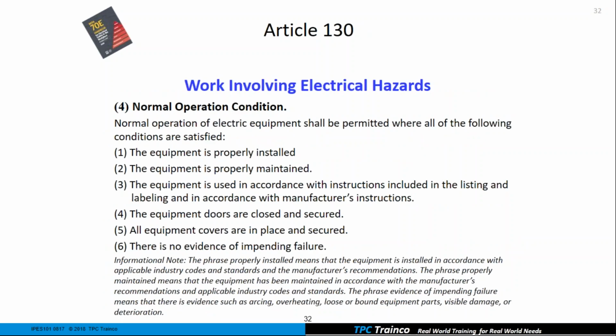Article 130, which is pretty much the heart of NFPA 70E, and the first change we see in there is normal operating condition. There used to be 5 conditions that we had to satisfy before we could go up and operate a piece of equipment normally, but now they've added one here. Number 1 was always there, properly installed. Number 2, always there, properly maintained. Properly maintained, by the way, in my opinion, is tough because it has to be maintained in accordance with the manufacturer's instructions and applicable industry codes and standards. I always use, for an example, a molded case circuit breaker. How many of us go out and test the torque on that once a year? We might do thermal imaging. How many of us meg that plastic out? So it's tough to get properly maintained, but hopefully we can strive to get there.